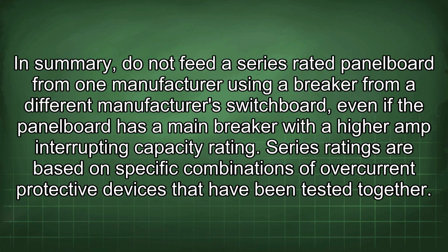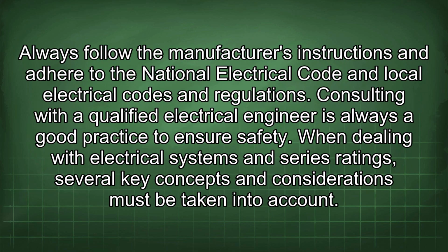In summary, do not feed a series-rated panel board from one manufacturer using a breaker from a different manufacturer's switchboard, even if the panel board has a main breaker with a higher amp interrupting capacity rating. Series ratings are based on specific combinations of overcurrent protective devices that have been tested together. Always follow the manufacturer's instructions and adhere to the National Electrical Code and local electrical codes and regulations. Consulting with a qualified electrical engineer is always a good practice to ensure safety.